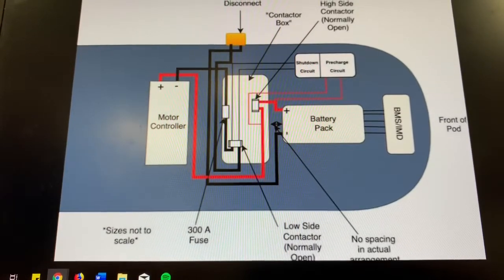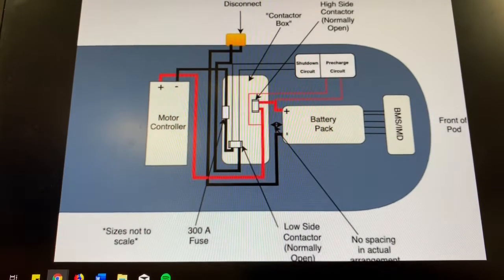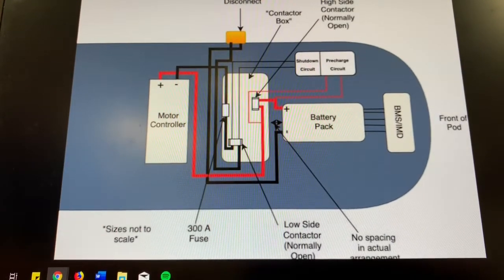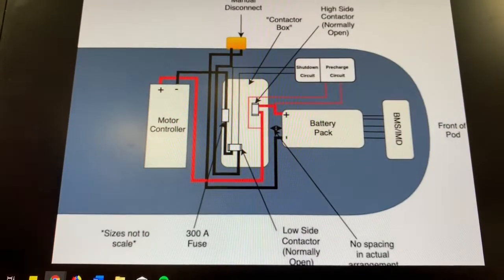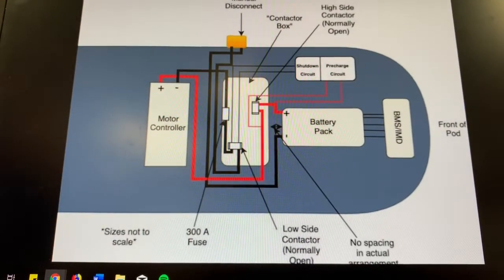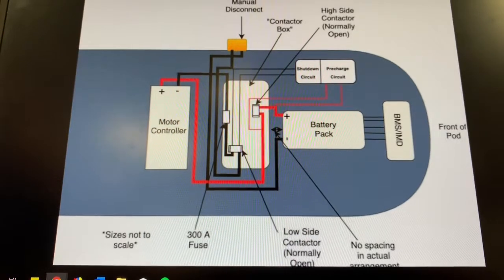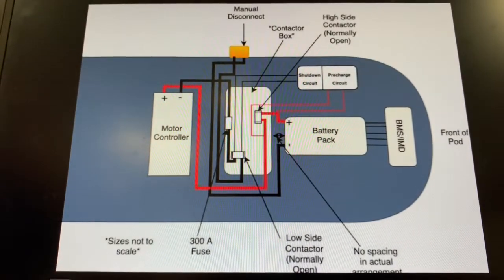The manual service disconnect is a required part of every pod, and its main utility is if both contactors were to fail, say fuse shut, and we cannot open the circuit any other way, this provides a means to do that safely.